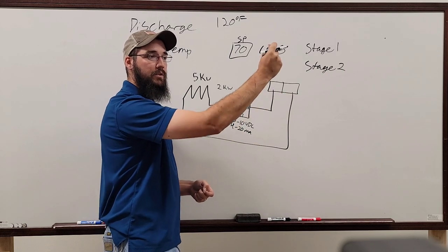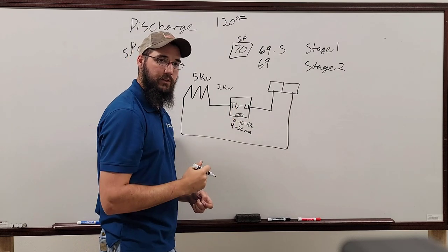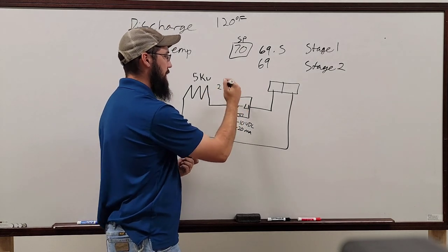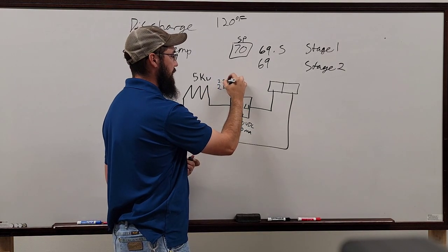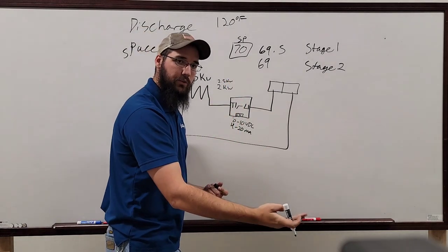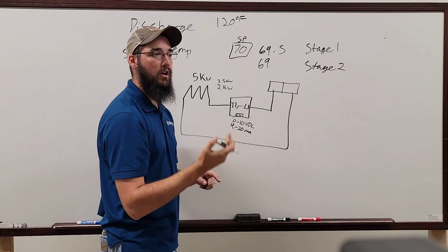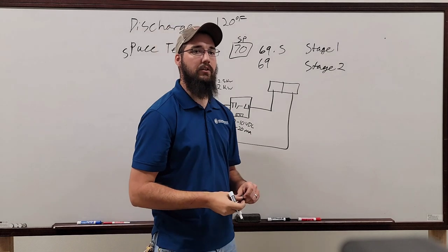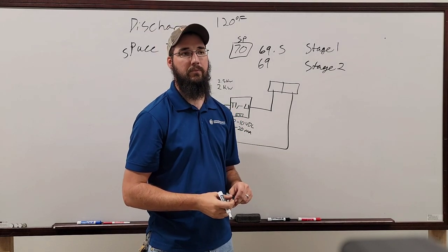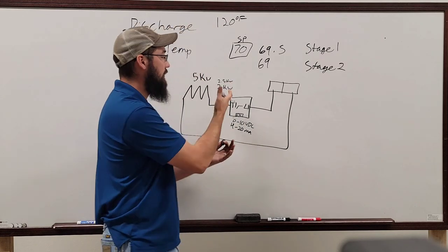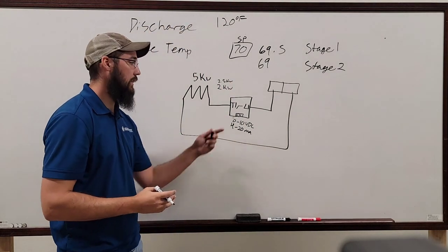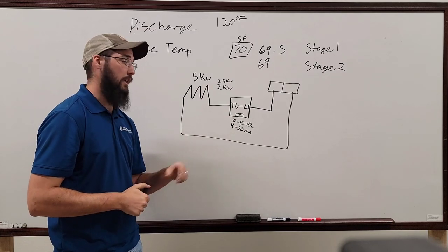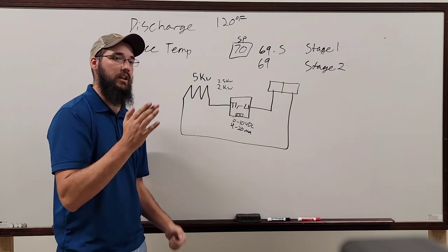But even at 2 kW, say we're still not able to keep up, and we drop another tenth of a degree, so we're at two-tenths below set point. We need more demand, so we step up to 2.5 kW, and so forth until we get low enough below set point that we eventually get to the full capacity of that heater. That's how we're using SCR heaters. They're a solid state relay that has a gate in them controlling that flow. By the time we get to max signal, that gate just slams closed.